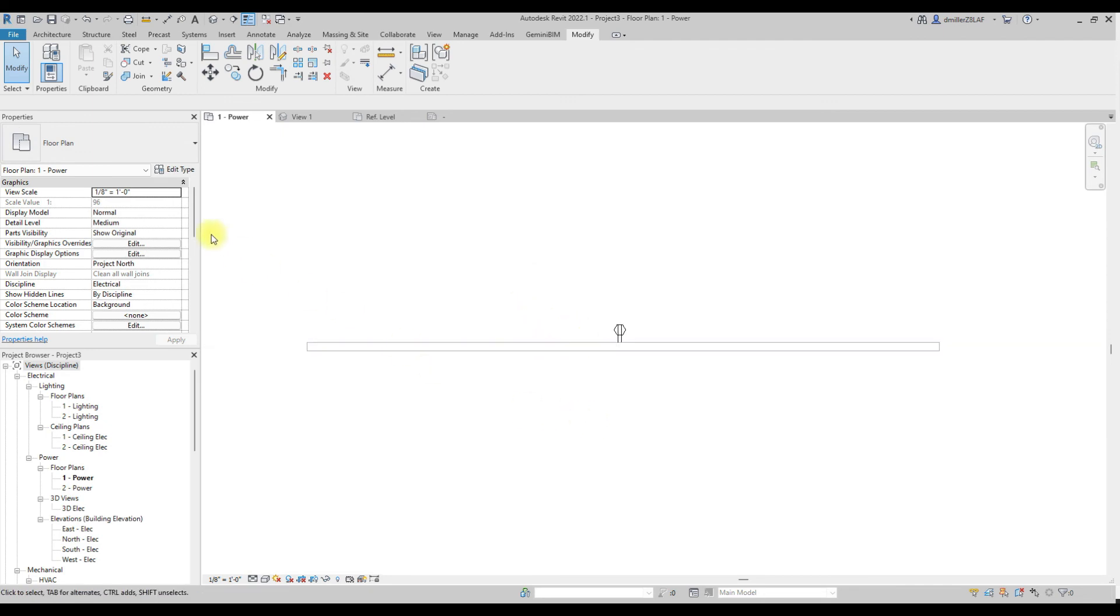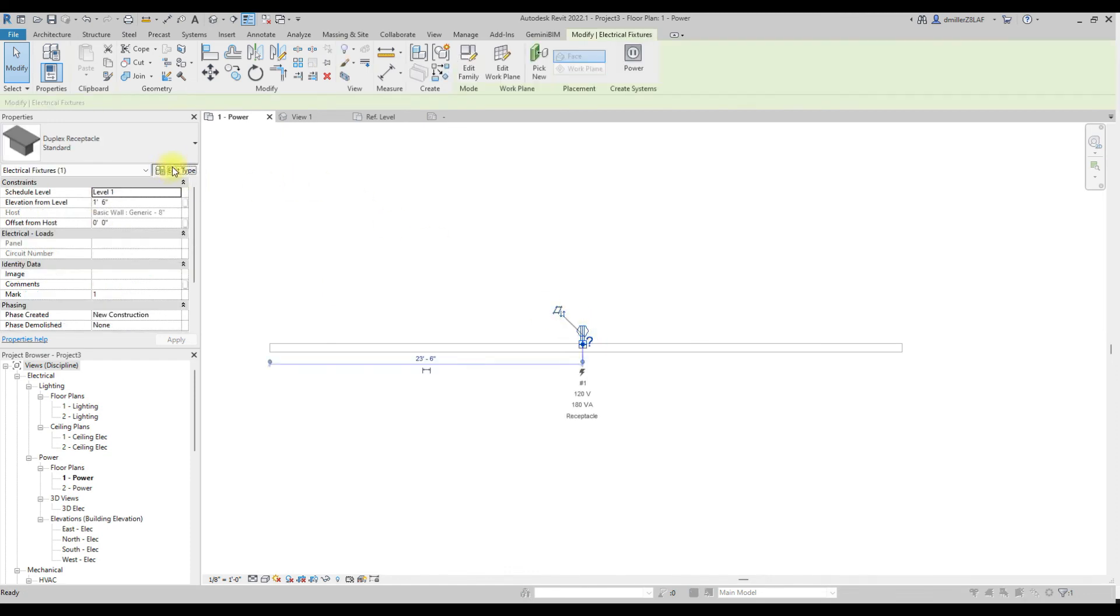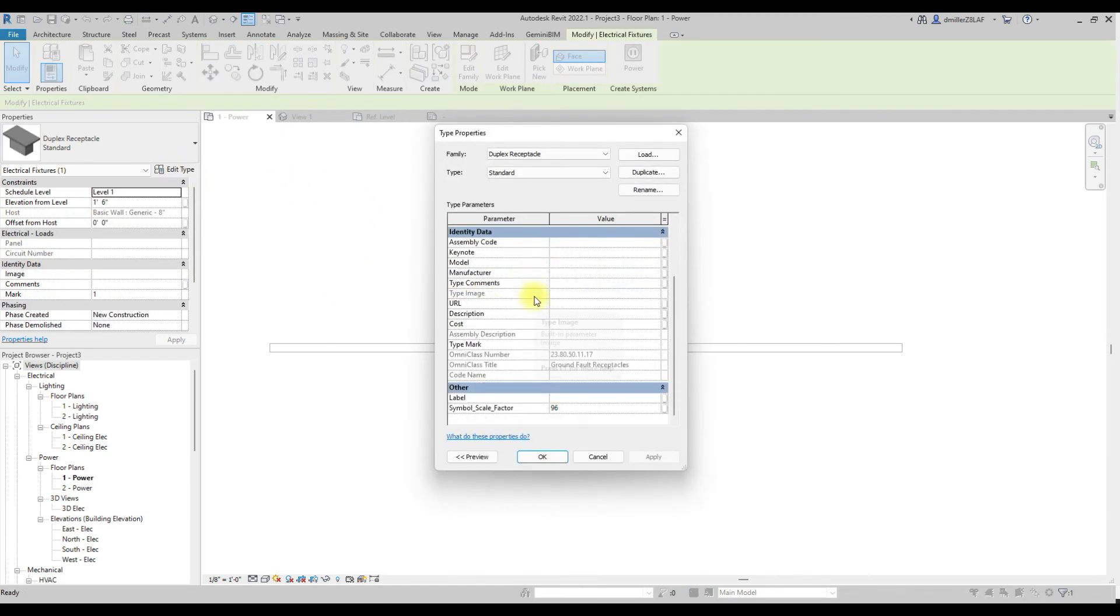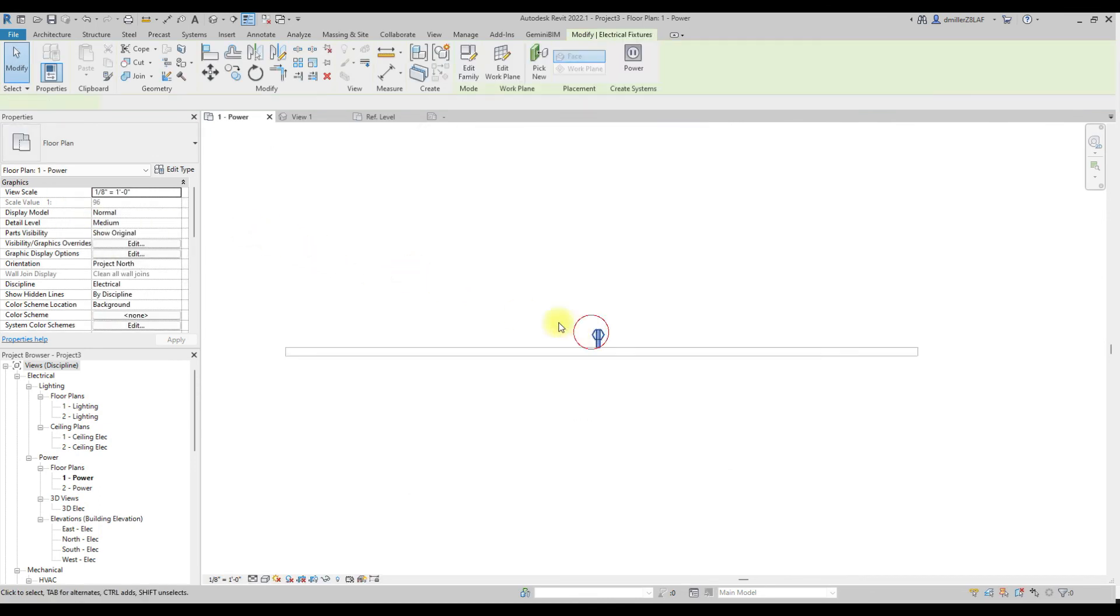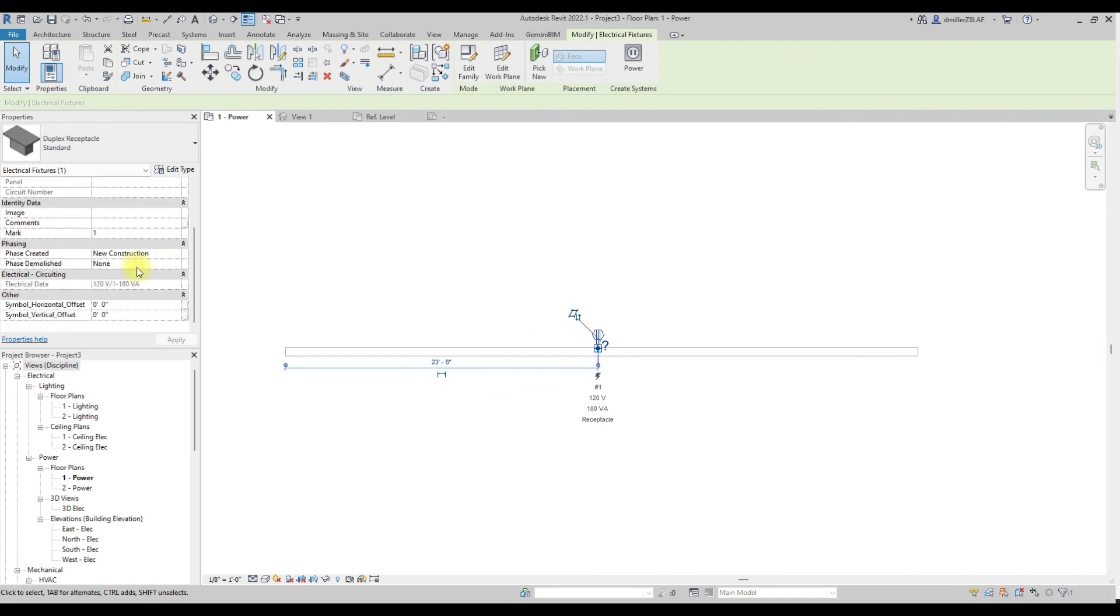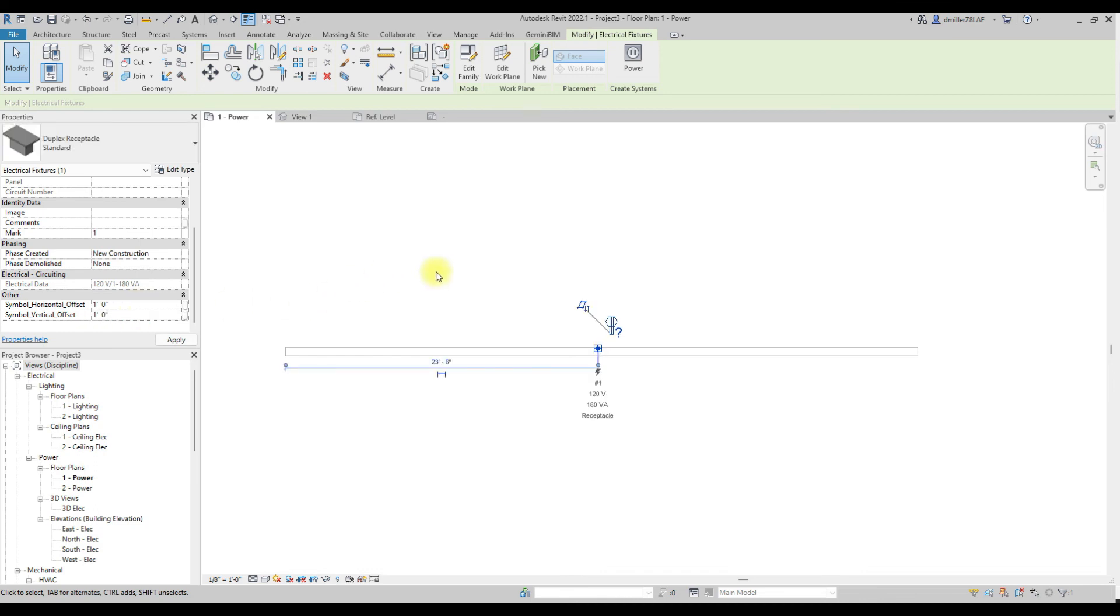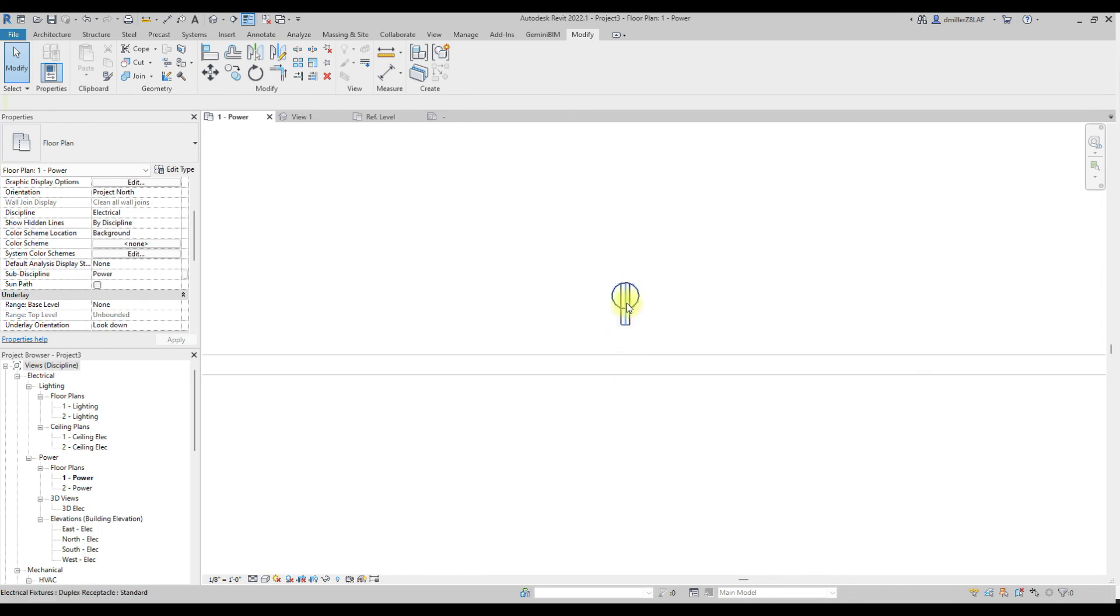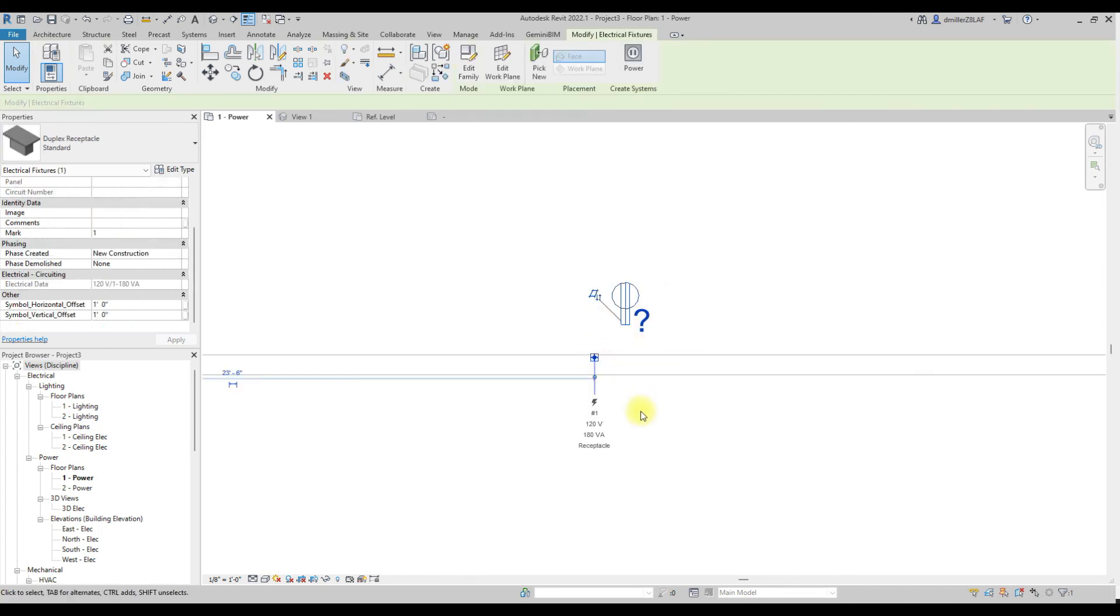So again, we're at a one eighth inch scale, which is typical for architectural and MEP drawings in the United States. And you can see a scale value of 96. And that's where this scale value comes into play. So we're at 96. So at the very bottom under other, we can test this out and specify a value. And because I am applying that 96 scale value, I know that it moved to the right one foot and up one foot. So you can see that our annotation is offset from our actual 3D device.